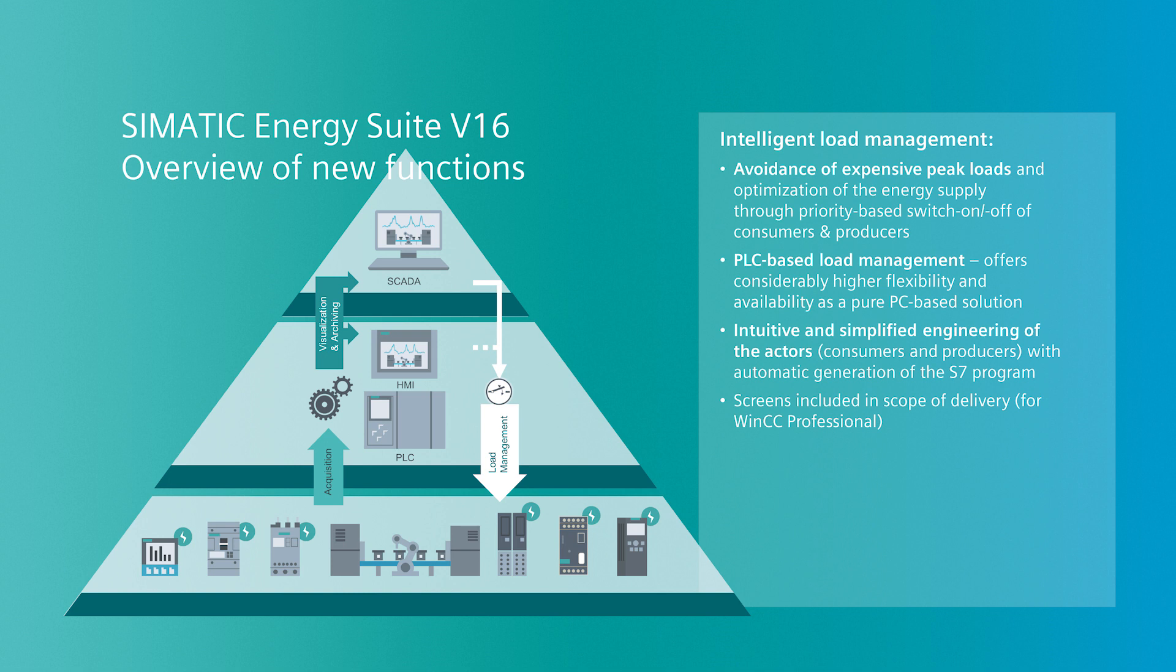The biggest innovation of the new Energy Suite version is the integrated peak load management. With this software, the user can avoid load peaks which affects high energy costs by switching energetic consumers and producers. The load management is running on S7-1500 controllers, and as already known from the SIMATIC Energy Suite, the PLC program will be generated automatically according to the configuration in TIA Portal. The visualization for both the system overview as well as for each actor will also be included in scope of delivery.